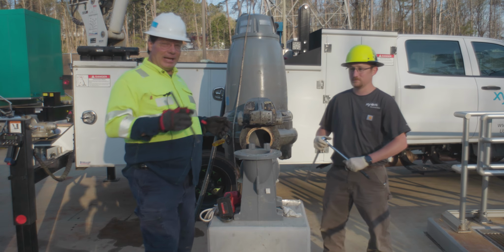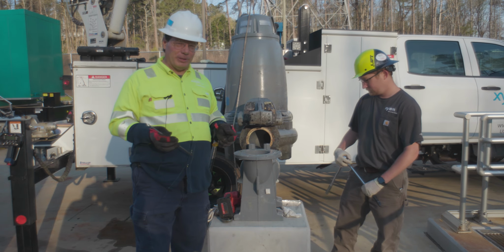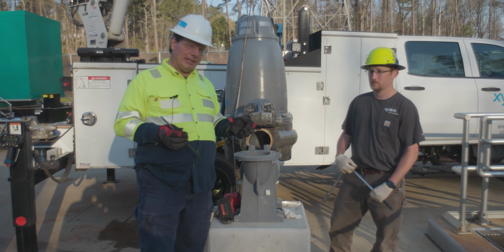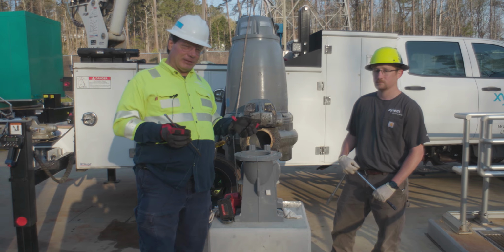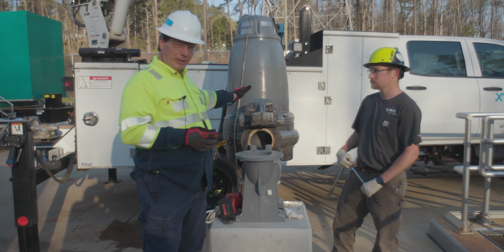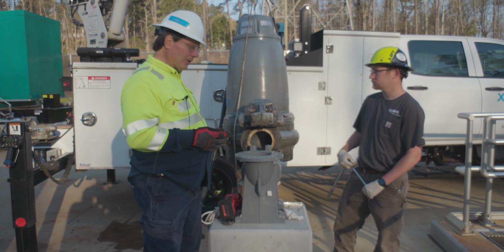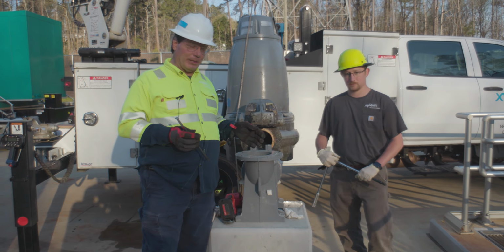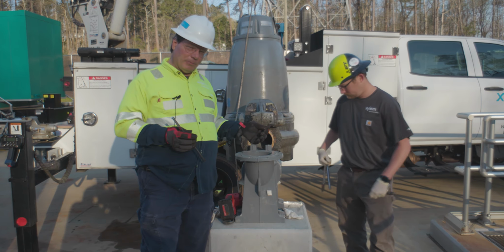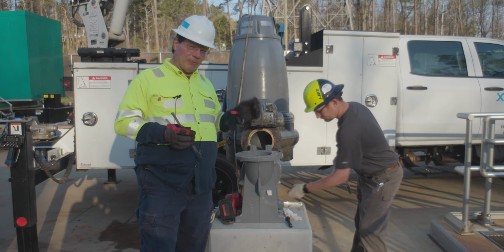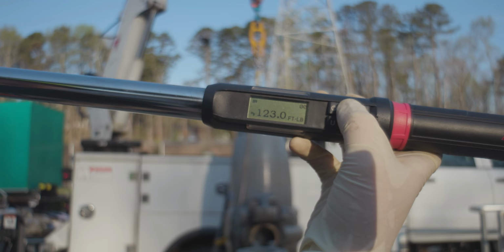All right, once we do that, then we'll put the 14 millimeter impeller bolt back in and tighten it to torque. And then once that's in, you don't torque the collet, you torque the impeller bolt, and that's what holds everything in place. So we'll put the impeller bolt back in, torque it, and then we'll be done with this impeller adjustment.